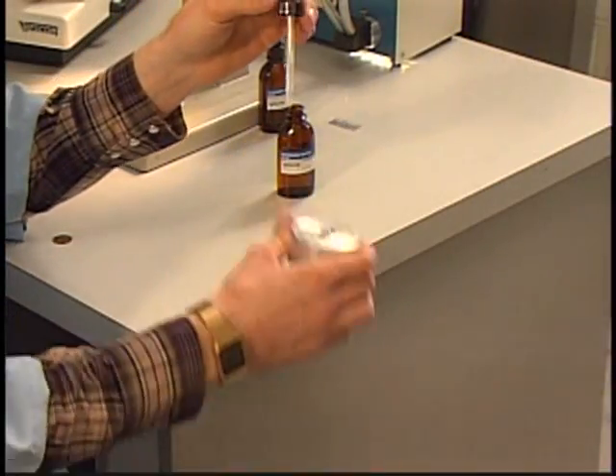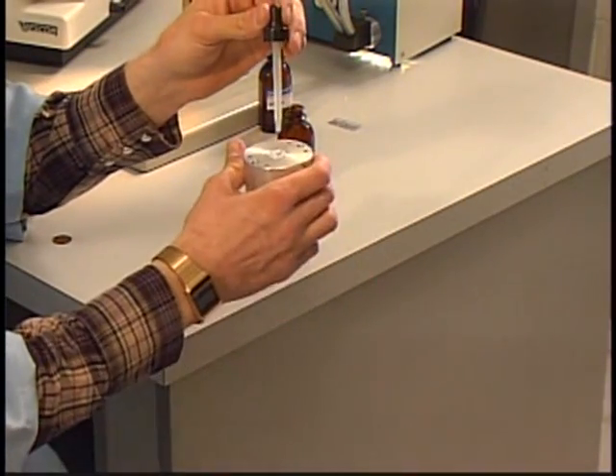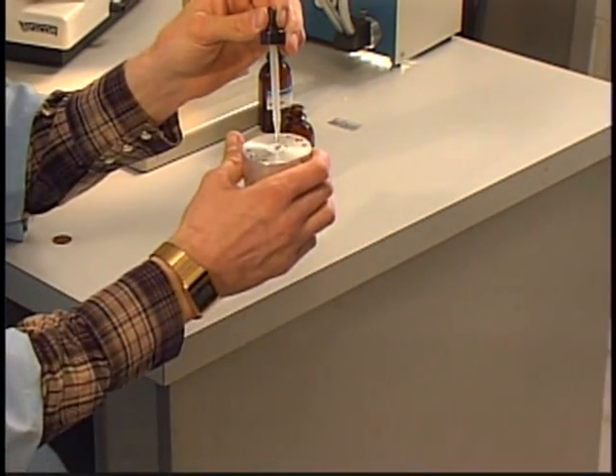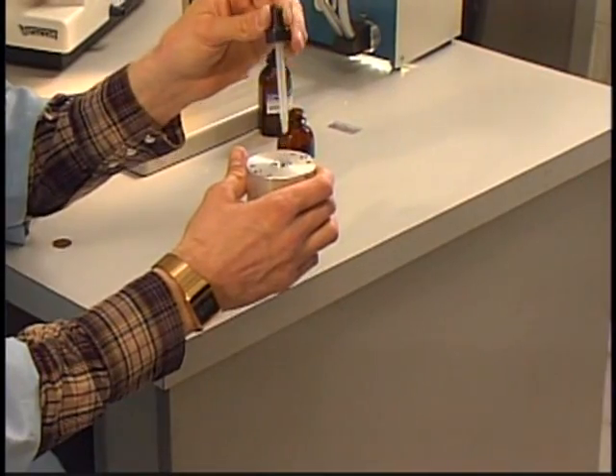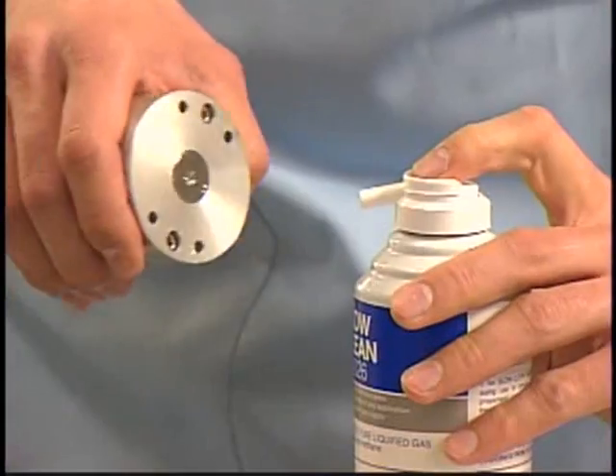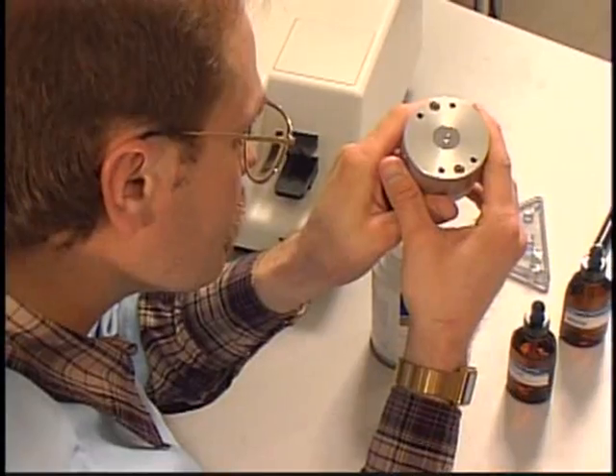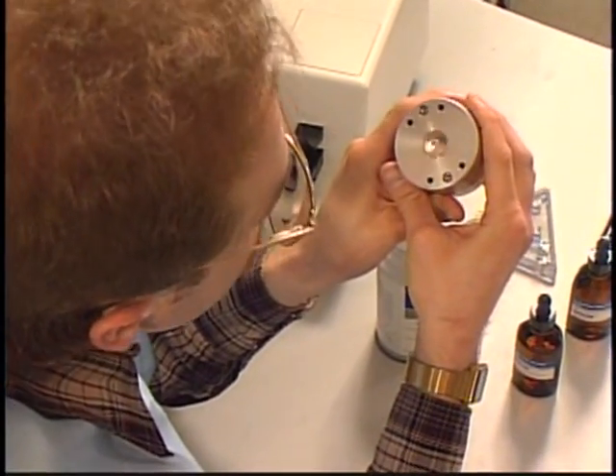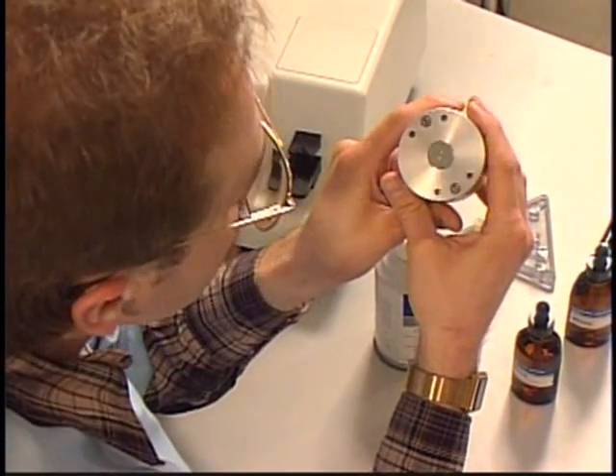Shake off the cleaning solution and immediately put on a few drops of deionized water. And shake it off. Drop on, shake off 10 times. Then blow dry. If the head still looks dirty or once again fails the clean test, it's time for serious action.